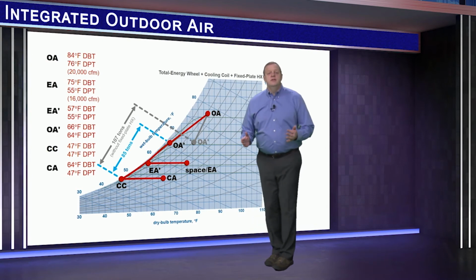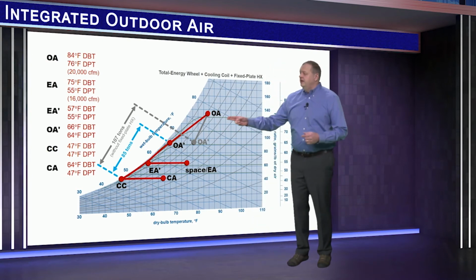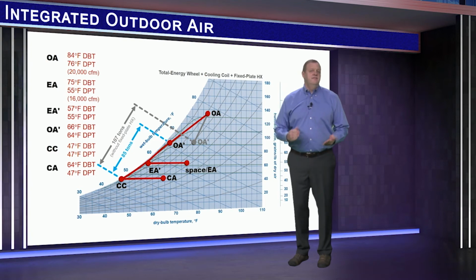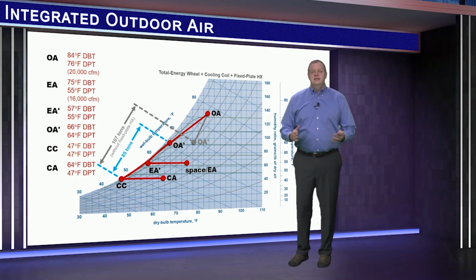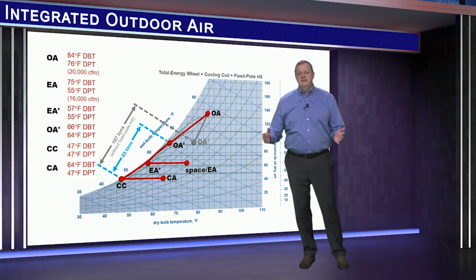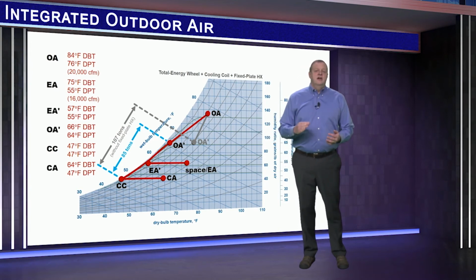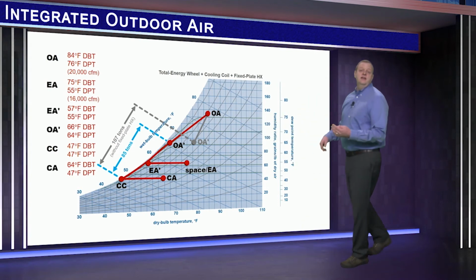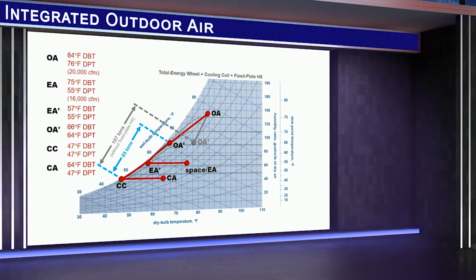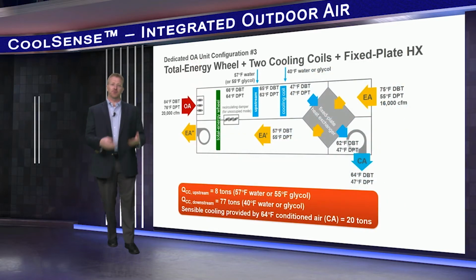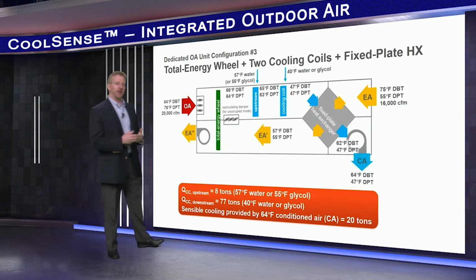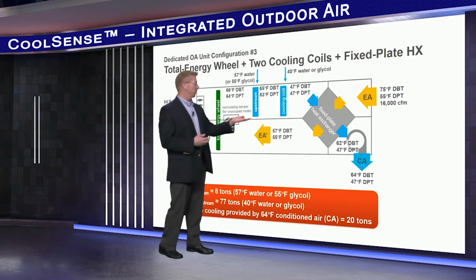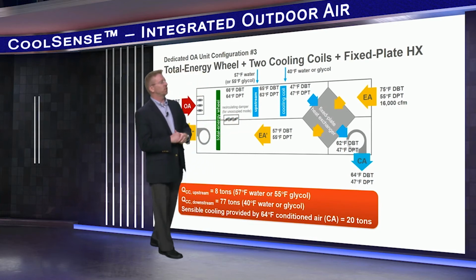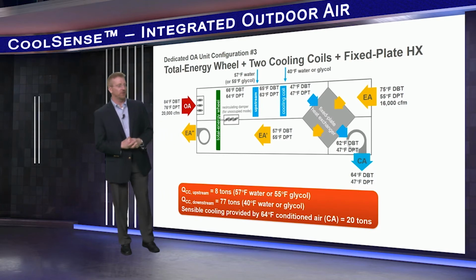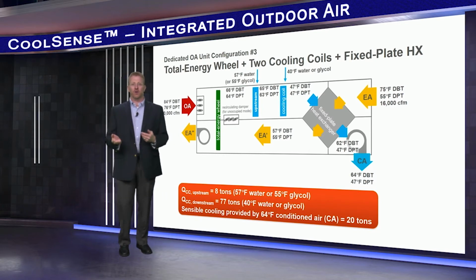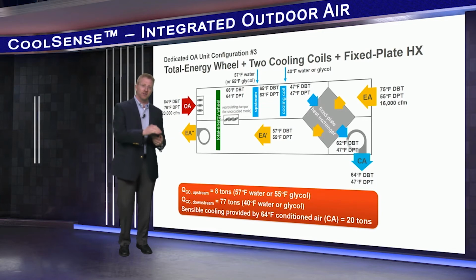Now this added pre-cooling benefit reduces the load on the cooling coil to 85 tons compared to 107 tons without it. But again, the fixed plate heat exchanger impacts the physical size of the unit and adds pressure loss. And the warmer air leaving it offsets even less of the zone sensible cooling load. And again, same as before, this configuration can also benefit from using separate chilled water coils in series. Here, 8 tons of cooling load is shifted to the warm water chiller, reducing the load from the cold water chiller from 85 tons to 77 tons.